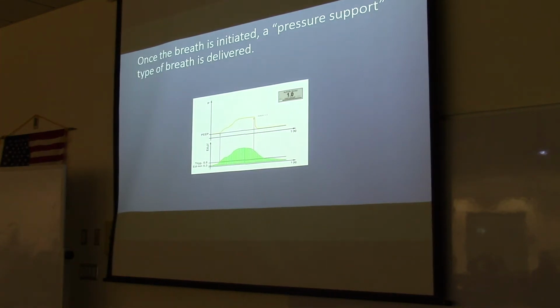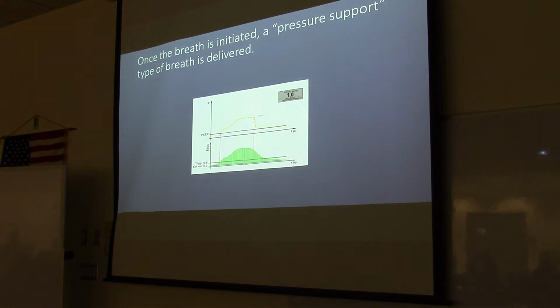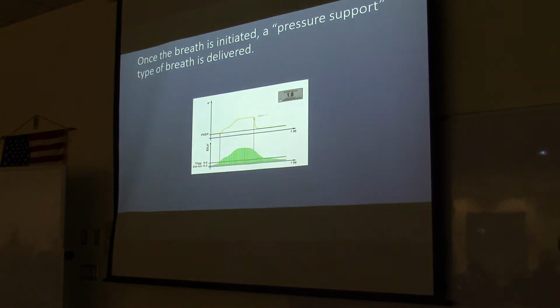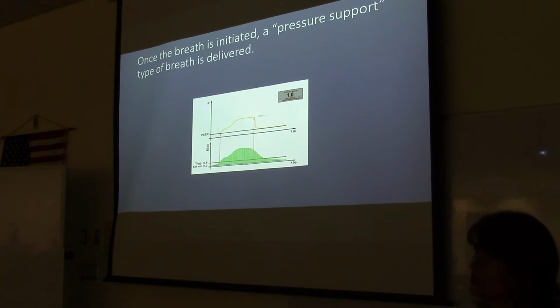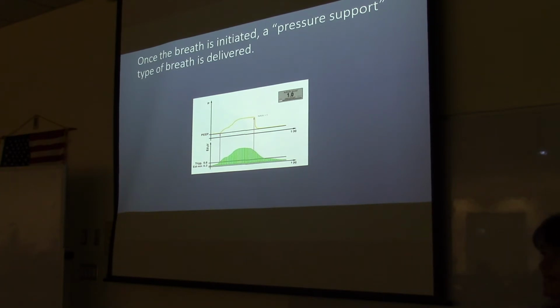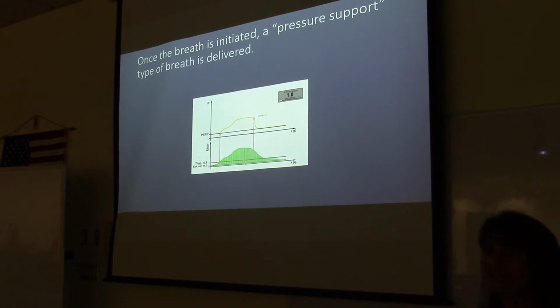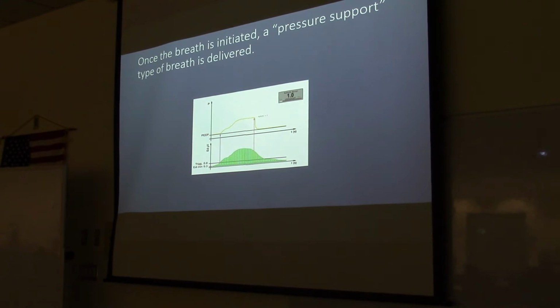So once the breath is initiated, a pressure support type of breath is delivered. So Nava is just a fancy pressure support. What makes it fancy is that it's going to deliver pressure support exactly when the patient wants it. Wow. So it synchronizes to the electrical activity, basically? That's all it's doing? Yeah, it sees an increase in electrical activity, so it gives pressure support. If it sees a lot of activity, it gives a lot of pressure support. A little activity, it gives a little pressure support. Wow, that's really interesting.